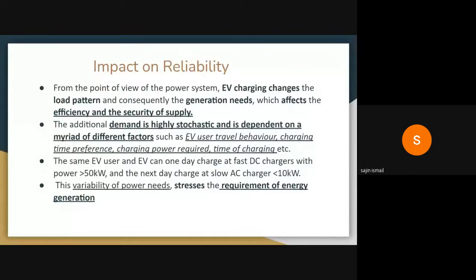A case example: an AC slow charger at home is less than 7 kW, taking 7 to 10 hours for a full charge. But if a user wants immediate charging, they may use a fast charger of 50 or 60 kW instead. So the power demand changes significantly, from an expected 3 kW or 7 kW to 30-40 kW transferred within an hour. The demand of power keeps changing at any time.